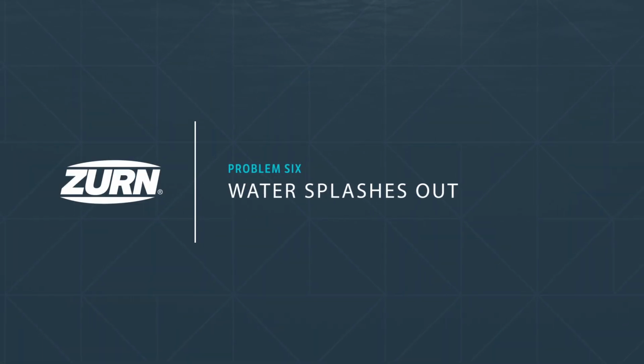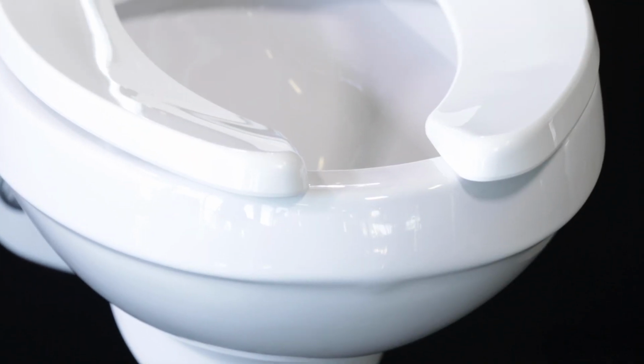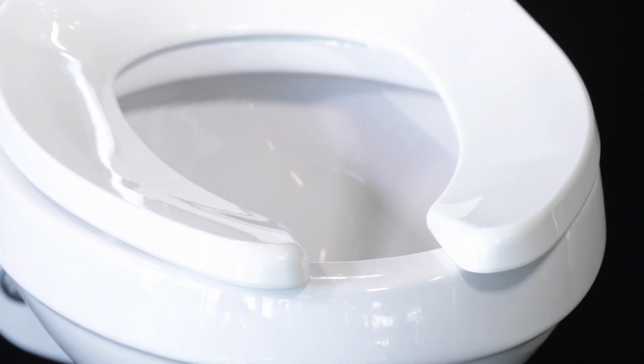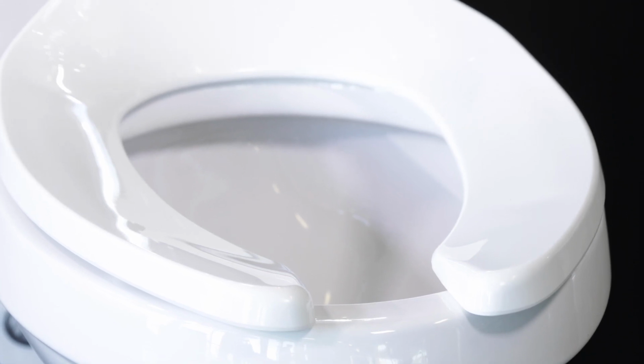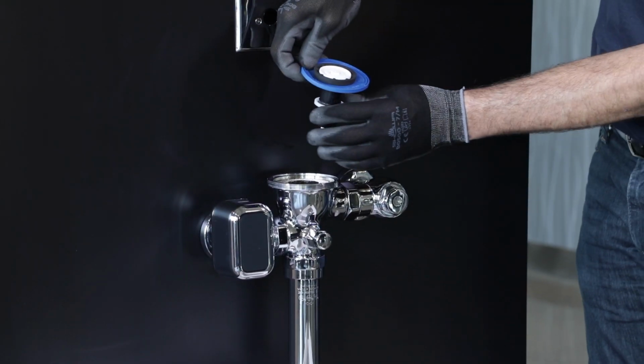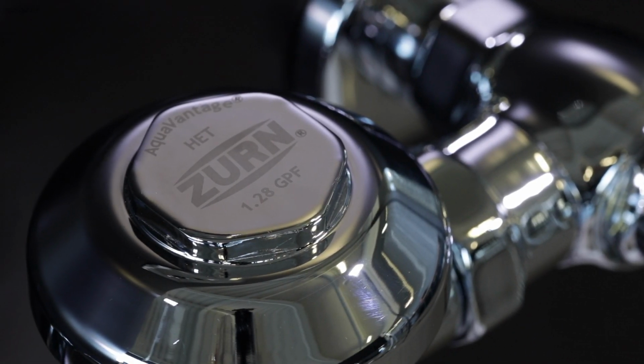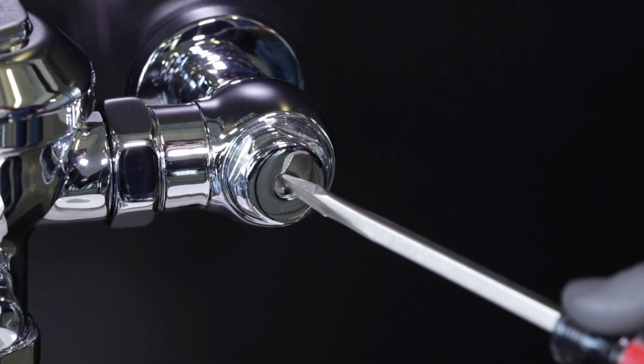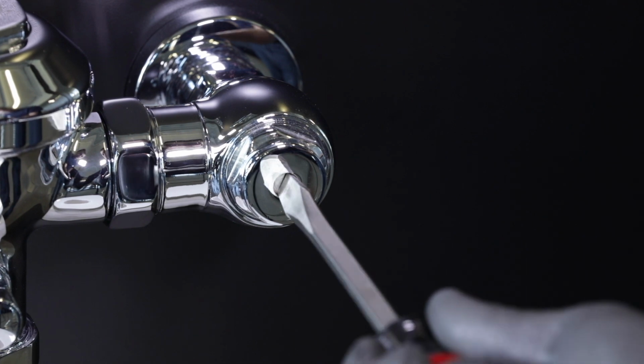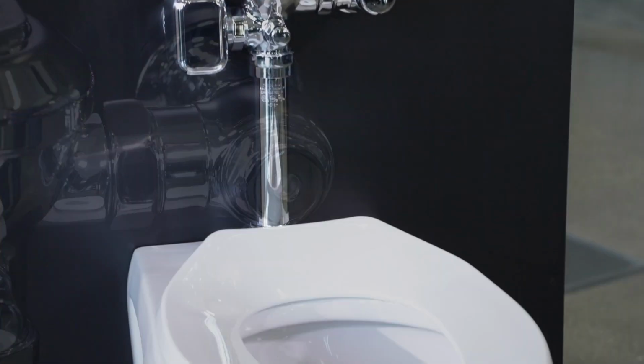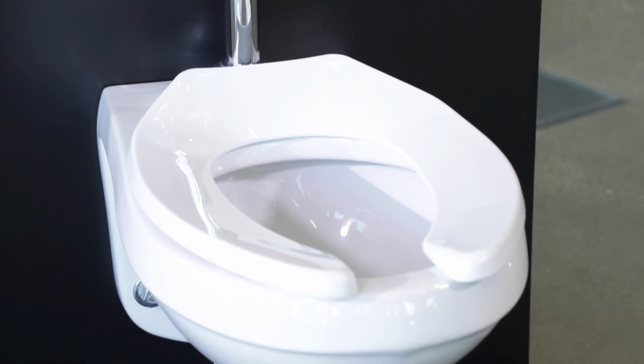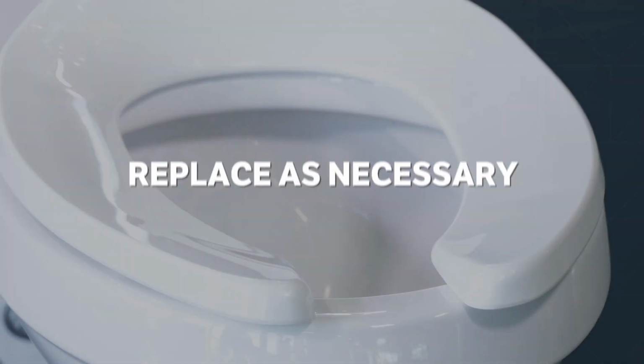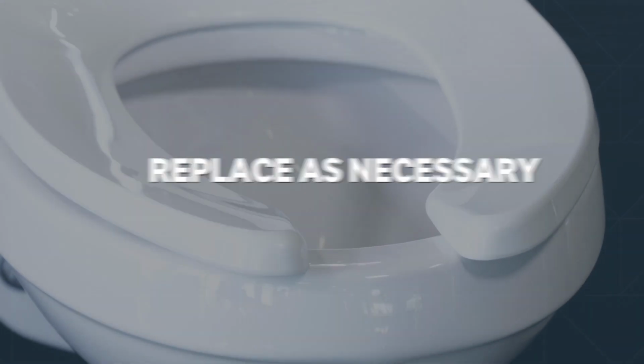Problem 6. Water splashes out. Water splashes out of the bowl when supply volume is more than necessary, or from lime accumulating within the bowl. Double-check the diaphragm for the volume to ensure it matches the volume of the fixture. Adjust the control stop, or replace the diaphragm with a lower volume kit as needed. Lime or calcium buildup in the vortex or the spreader holes can be rather tricky to remove. You may need to completely replace the fixture.